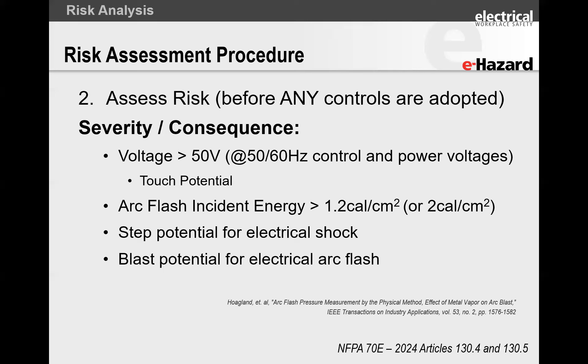There's a peer-reviewed paper I've added here that addresses why people should use arc rated clothing. People said, 'If there is an arc flash, the blast is going to kill me.' No. All of the science has proved otherwise. In every accident investigation that we have performed, not one instance was the blast the cause of the fatality. In most instances, it's the body giving up from respiratory complications. Then it's the non-arc-rated clothing — your polycotton t-shirts, polycotton shirts, regular non-arc-rated denim jeans — catching light and burning people. Get your arc rated clothing.